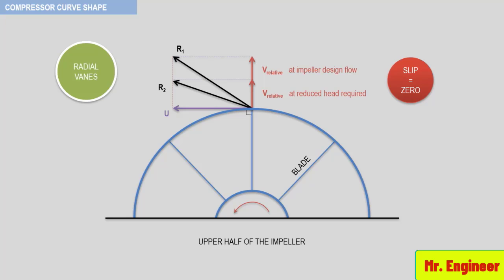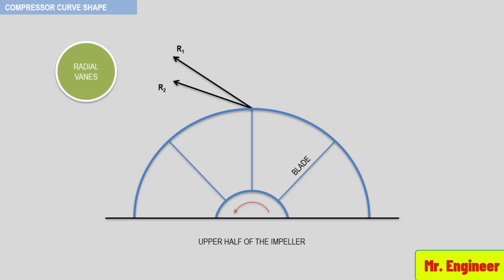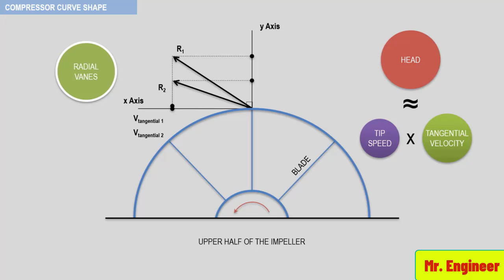Notice that since the relative velocity follows the radial blade path, the magnitude of the tangential velocities of R1 and R2 remains constant regardless of the value of relative velocity. Resolving R1 and R2 into X and Y components, it becomes clear that the two tangential velocities are identical. Since the head generated by the blade is the product of tip speed — unchanged — and tangential velocity — also unchanged — the design head produced in a radial impeller will remain essentially constant.